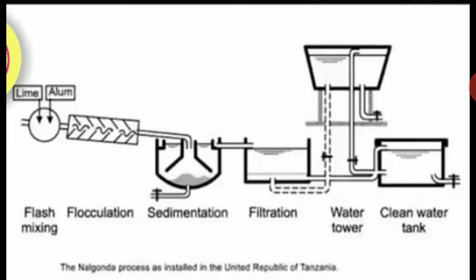Defluoridation is the removal of excess fluoride from the water. Some excess percentage of fluoride may be present in the water that should be removed. The desirable limit of fluoride is 1 ppm and the permissible limit is 1.5 ppm. The fluoride level should be less than 1 ppm, and in worst conditions up to 1.5 ppm can be acceptable.